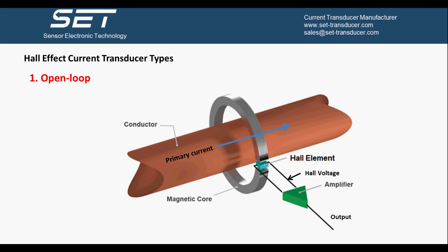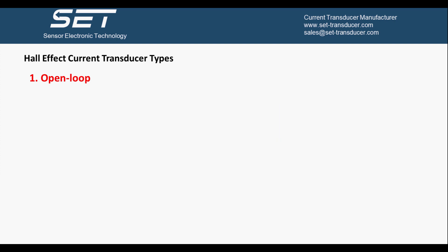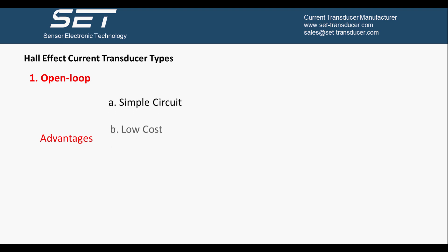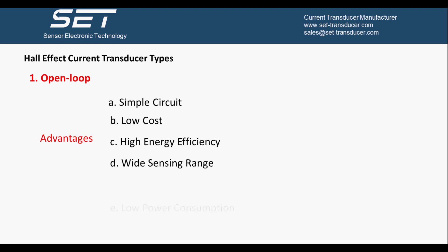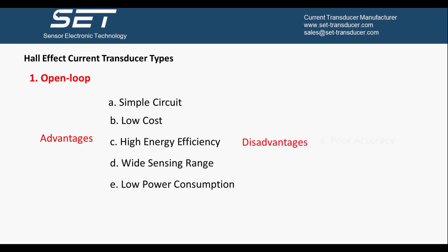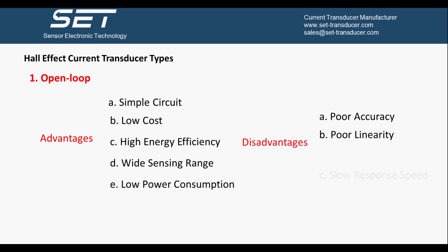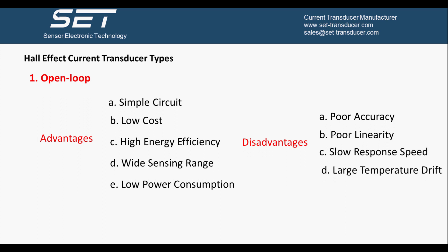The advantages of the open loop Hall Effect current transducer are simple circuit, low cost, high energy efficiency, wide sensing range, and low power consumption. The disadvantages are poor accuracy, poor linearity, slow response speed, and large temperature drift.